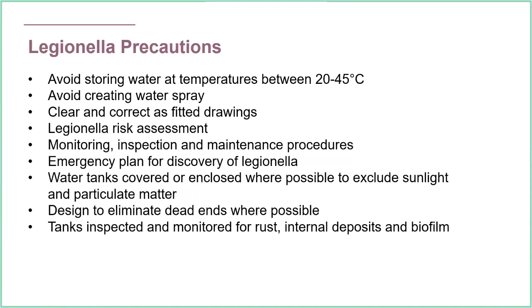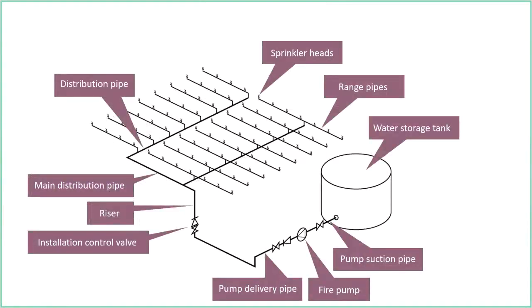Designed to eliminate dead ends where possible - that was taken from a reliable source, though I suppose it's more suitable for plumbing installations. If we go back to our diagram, in a sprinkler system we've effectively got dead ends all over the place, because that's just the nature of the system. It's quite unusual to have systems linked together into a loop, so the vast majority of range pipes are going to be dead ends - there may be drains at the end, but they're rarely used. So yes, there are going to be a lot of dead ends created - I did smile when I saw that recommendation, really.